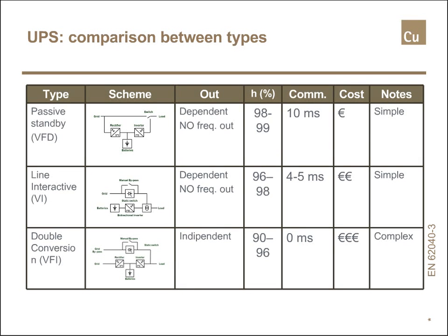Line interactive is again quite simple, costs a bit more than a passive standby, and we still have a dip when moving from grid to battery operation. The output is dependent on the input only from the point of view of frequency. The last line is dedicated to double conversion. This is the most complex layout, the cost is the highest, we don't have any dip moving from grid to battery operation, and the output is fully independent from the input.